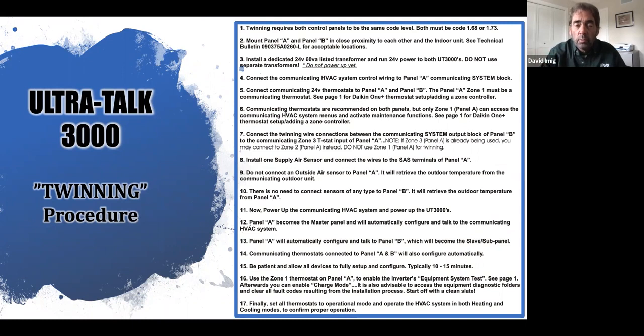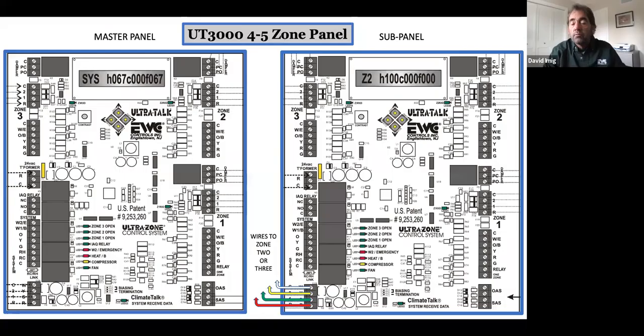Just released to you, I believe around 3 weeks ago, was the ability to twin, which now we can go up to 5 zones. We did put an addendum in with these UT-3000 boxes with the installation manual that goes through the information on how to twin these. So you'll note that we'll use identical boards. One's a master panel, one's a sub panel. We do not end up with 6 zones. Even though we're using 2 3-zone boards, we end up with an additional 4th zone or an additional 5th zone. The 6th zone will be utilized with connecting these 2 together or twinning it together. So zone 2 or zone 3 will be used to twin. So you lose that particular zone, which now takes this twinning down to a 5-zone max.